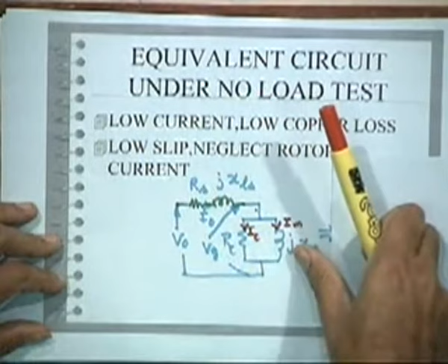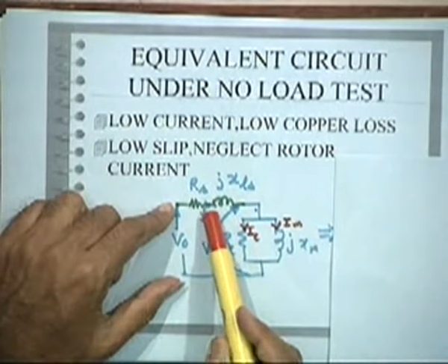So your circuit will typically look like this. Your equivalent circuit under no load will be - you only maintain the stator impedance RS, JXLS, and the rotor you neglect, because rotor current is 0. Only you maintain the magnetizing branch and the core loss branch. And so the voltage per phase is V0, current per phase will be I0, and the power per phase you can say is P0. So these are the things which you are measuring - voltage, current and power.